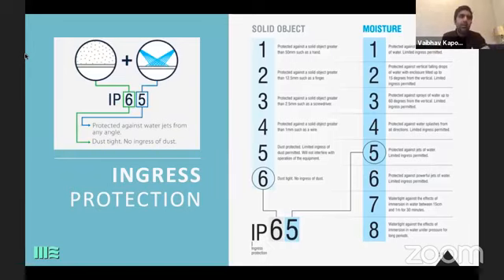So every equipment which is made abroad or what we buy off the shelf, certain things are IP65, there are IP67 also. The first number, 6, says that it should be dust tight, with no ingress of dust. So all your electrical equipment for temporary power distribution has to be IP6 and then the 5. 5 means that it is protected against jets of water, limited ingress permitted.